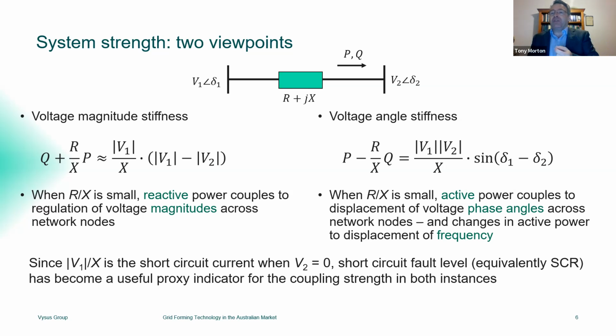And of course, when you look in particular on the right-hand side at the behaviour of phase angles, what you see is that as power flows change, we get a change in the separation of those phase angles, and if that's allowed to continue, then that can actually translate to movements in the system frequency as well, because the frequency is just the rate of change of those phase angles as we see them evolve in time. So there at a fundamental level, before you even talk about machines, we're talking about a relationship between active power flows in the network and perturbations in the system frequency.